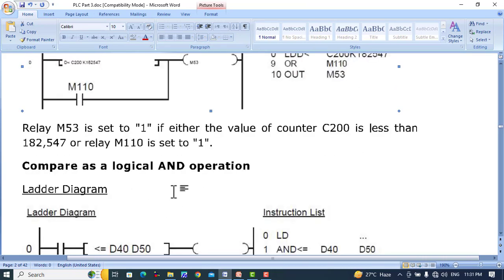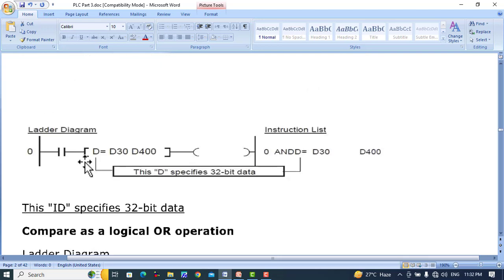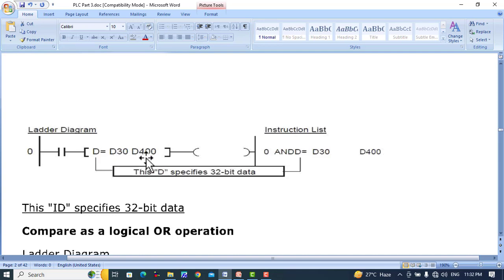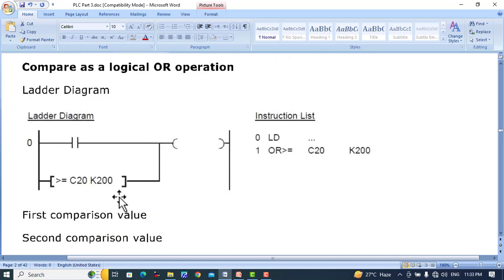Comparison as a logic AND operation: we can compare two values within an AND logic operation. Here you can see an input followed by a comparison of less-than-or-equal-to between two data registers — when the value of the first register is less than or equal to D50, the output will be turned on. A 32-bit AND example uses 'D' before the comparison: D30 and D31 data is compared with D400 and D401. When the value of D30 and D31 equals D400 and D401, the output is set to 1.